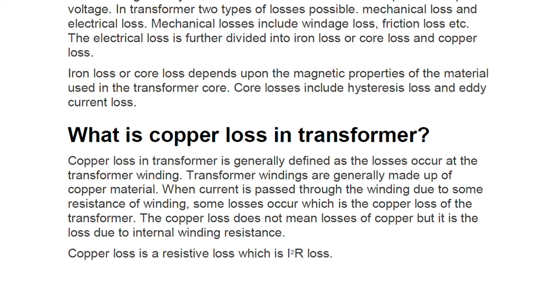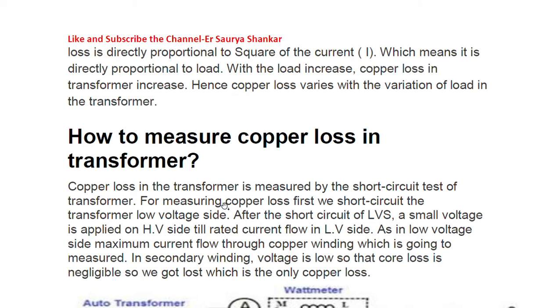Copper loss is an I²R loss. In the primary winding it is I₁²R₁, and in the secondary winding it is I₂²R₂, because the current and resistance are different in each winding. Loss is directly proportional to the square of the current, which means it is directly proportional to the load. The heavier the load (equipment), the more current it draws — for example, a mobile phone charger draws less current than a press or refrigerator.